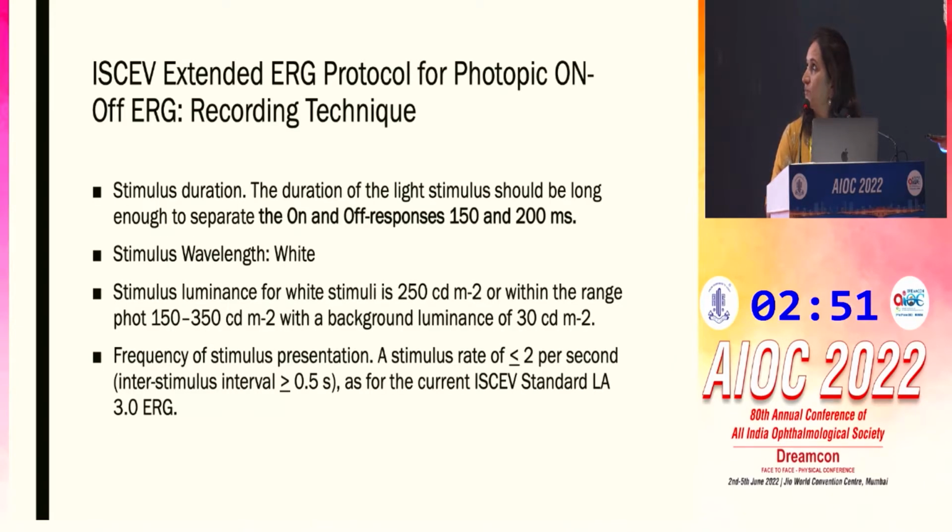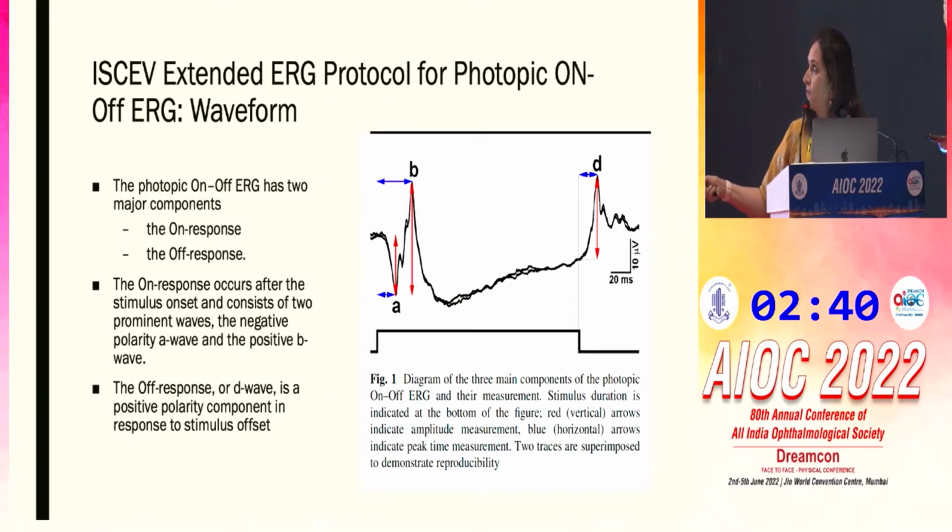Here the stimulus duration is increased to almost 150 to 200 milliseconds, when the normal duration is almost 5. So this is a very increased duration. And when you have this kind of long duration, and as the name suggests, it is done under photopic conditions, your response is something like this. This is the long duration response.